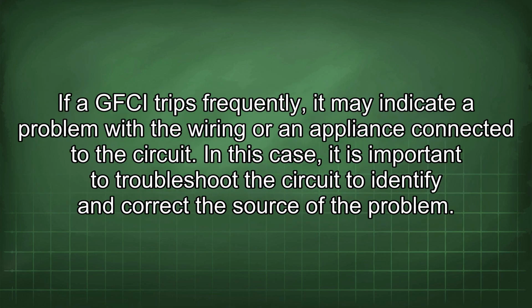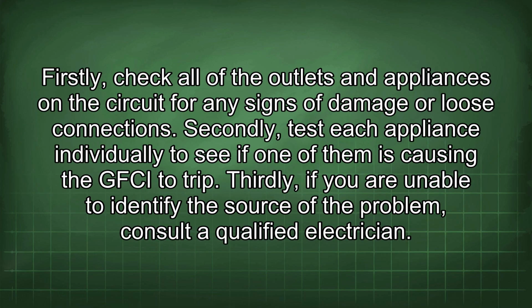If a GFCI trips frequently, it may indicate a problem with the wiring or an appliance connected to the circuit. In this case, it is important to troubleshoot the circuit to identify and correct the source of the problem. Firstly, check all of the outlets and appliances in the circuit for any signs of damage or loose connections. Secondly, test each appliance individually to see if one of them is causing the GFCI to trip. Thirdly, if you are unable to identify the source of the problem, consult a qualified electrician.